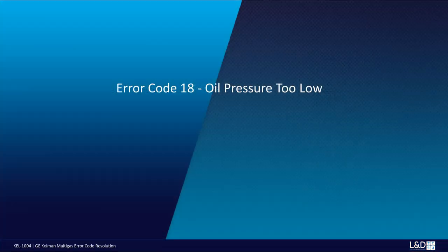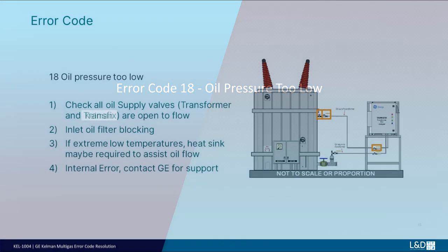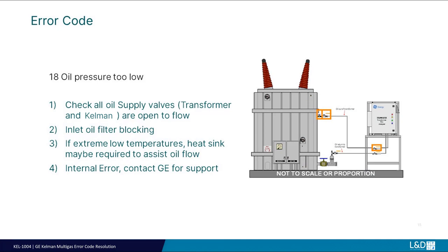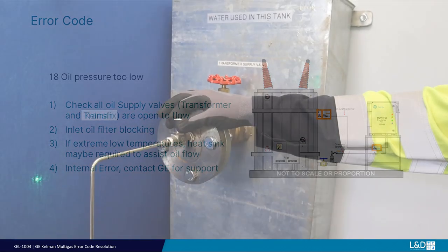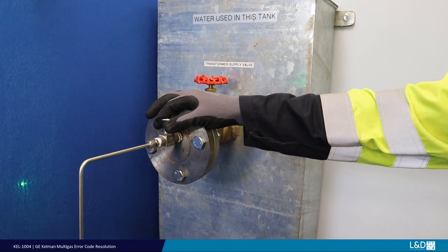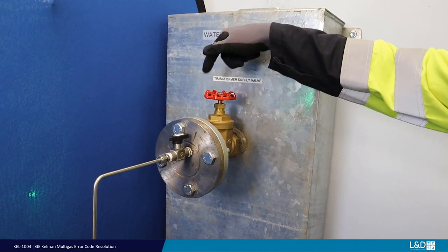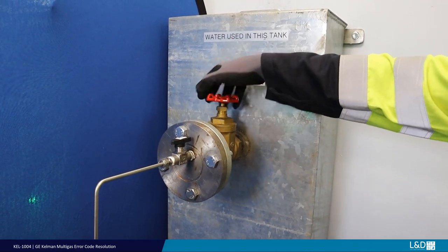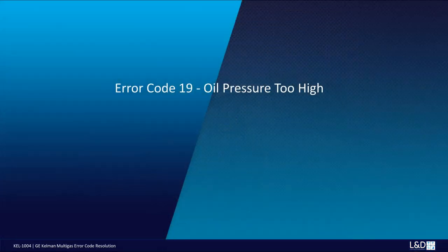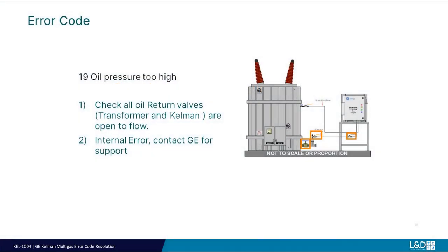Error code 18: Oil pressure too low. Check all transformer and Kelman fitted oil supply valves are fully open to flow. Check the inlet oil supply filter condition. Check for any excessive oil leaks. If fitted, any inline oil return filters are clean.